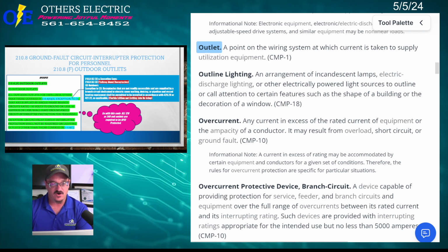Exception: ground fault circuit interrupter protection shall not be required on lighting outlets other than those covered in 210.8(C). Okay, so lighting outlets, not included. These are outdoor outlets other than lighting outlets. Let's get into this. So this is my note. So with this code, all 120 or 240 volt outlets are required to be GFCI protected.